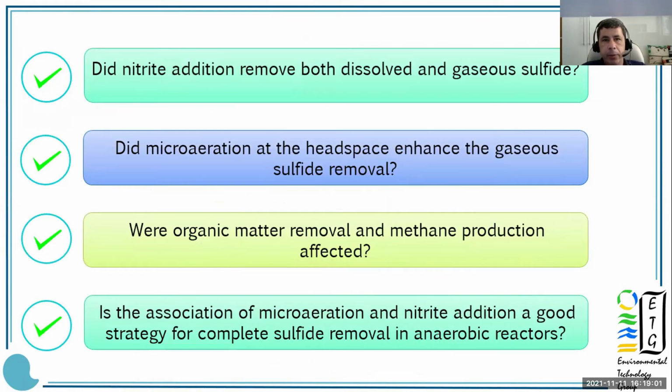Did nitrite addition remove both dissolved and gaseous sulfide? Yes, but more for the dissolved fraction. Did microaeration at the headspace enhance the gaseous sulfide removal? Yes, especially combined with the application of nitrite. Were organic matter removal and methane production in terms of millimole per day affected? No. And is the association of microaeration and nitrite addition a good strategy for complete sulfide removal in anaerobic reactors? Yes.